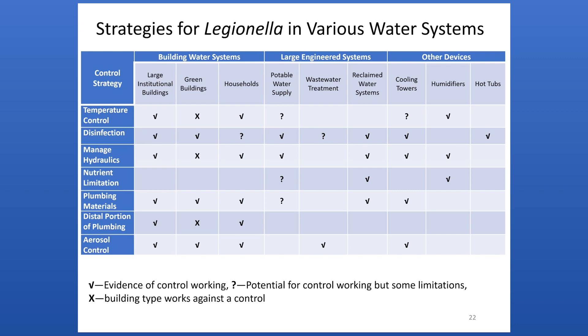Hot water heater temperature must be above 60 degrees C, and the hot water temperature at the distal points of plumbing systems should exceed 55 degrees C. There's ample evidence in many large buildings that keeping water temperature outside the preferred growth range of Legionella is very effective. That preferred range is 25 to 43 degrees C, so you've got to keep cold water below 25 and hot water above 43. Studies suggest 60 degrees C and 55 degrees C will prevent Legionella from growing in your building—a very important recommendation that will come up again later.